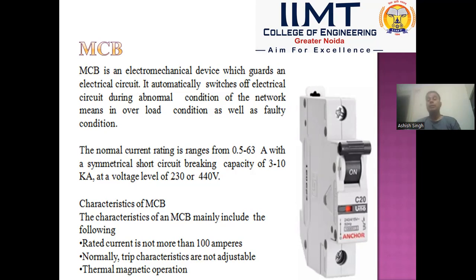The normal current rating for MCB is from 0.5 ampere to 63 ampere with a symmetrical short circuit breaking capacity of 3 to 10 kiloampere at a voltage level of 230 volt or 440 volt. 230 volt is in case of single phase AC supply, and 440 volt is in case of three phase AC supply. The main characteristics of MCB include the following points.